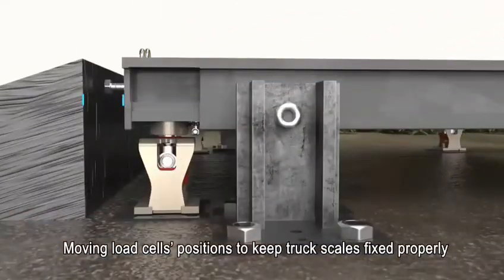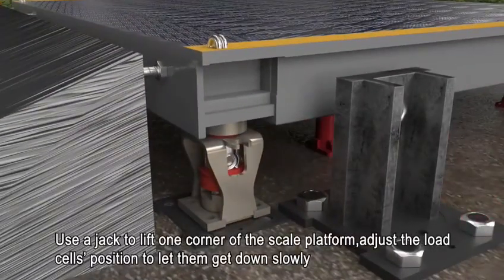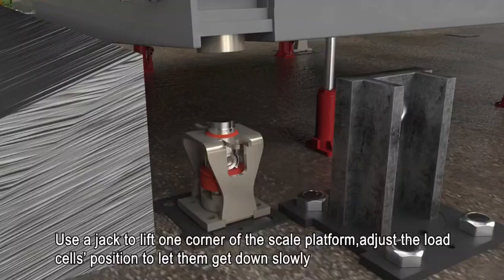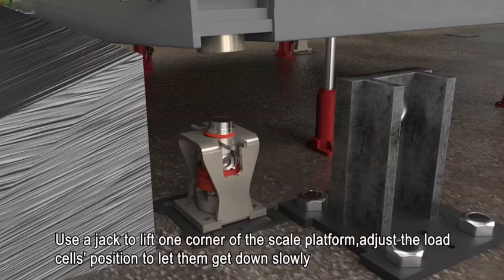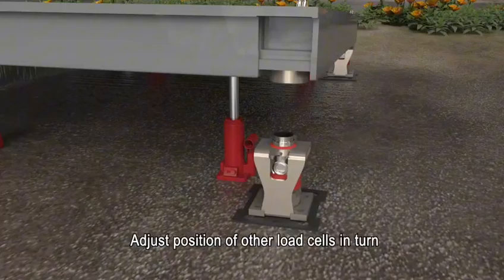Moving load cells positions to keep truck scales fixed properly. Use a jack to lift one corner of the scale platform. Adjust the load cells position to let them get down slowly. Adjust position of other load cells in turn.